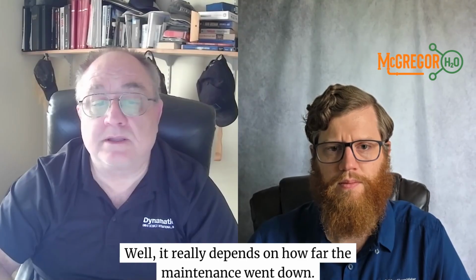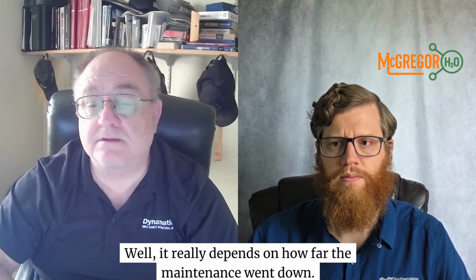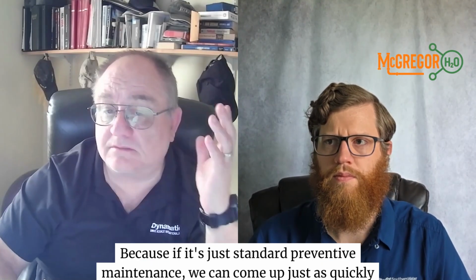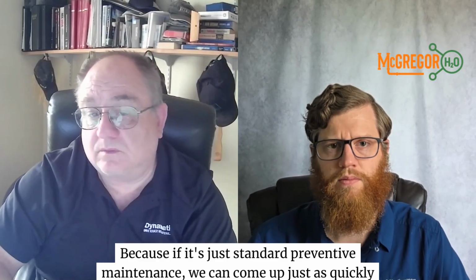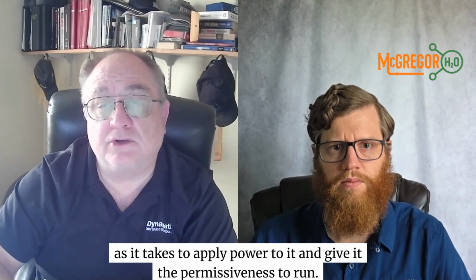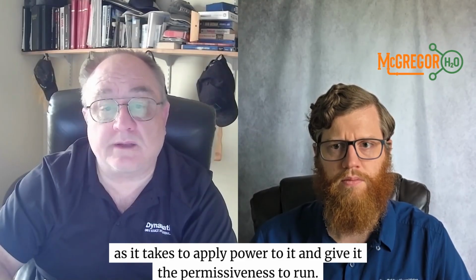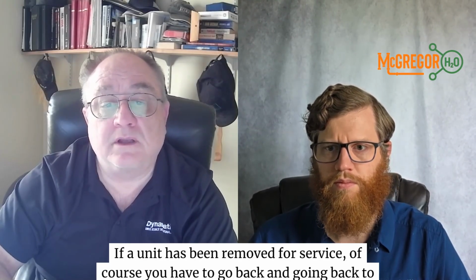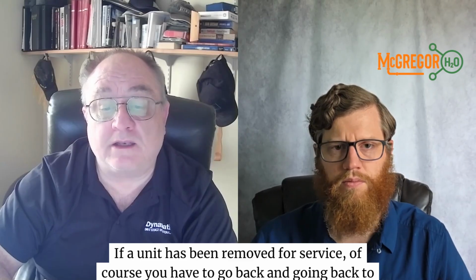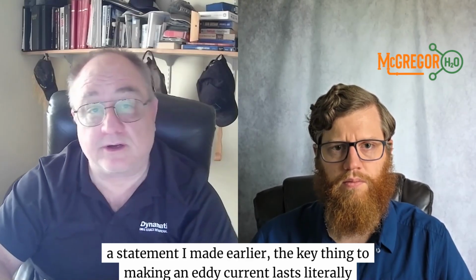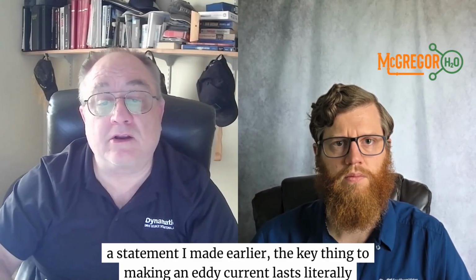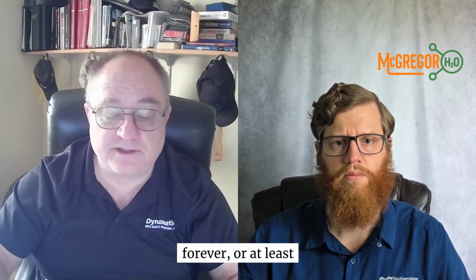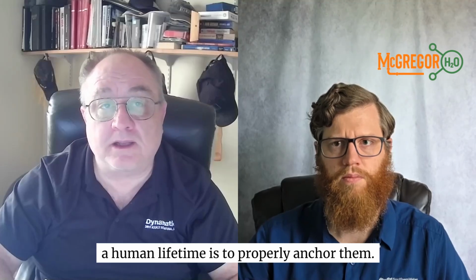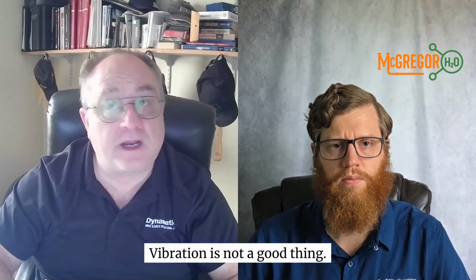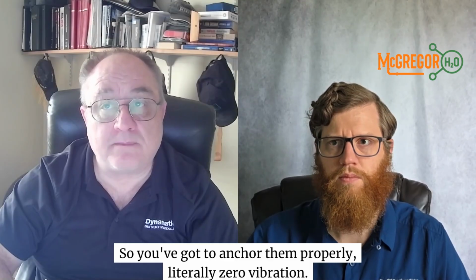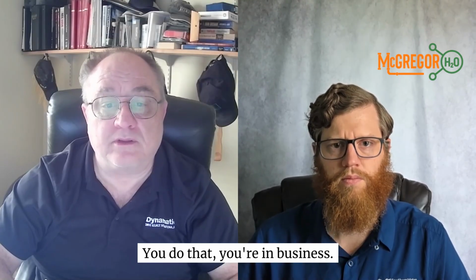Well, it really depends on how far the maintenance went down, because if it's just standard preventive maintenance, we can come up just as quickly as it takes to apply power to it and give it the permissive to run. If a unit has been removed for service, of course, you have to go back, and going back to a statement I made earlier, the key thing to making an eddy current last literally forever, or at least a human lifetime, is to properly anchor them. Vibration is not a good thing. So you've got to anchor them properly, literally zero vibration. You do that, you're in business.